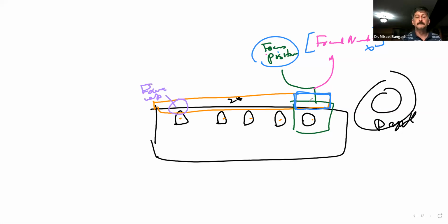Did that make sense? Good. If you say focal pause, it's not going to be written as the whole number, focal position. FOC for focus, POS for position. But if that is outside the bracket and you twist and turn this knob here, you actually can move your focal point up to a shallower depth, or you can move the focal point down to a deeper depth.